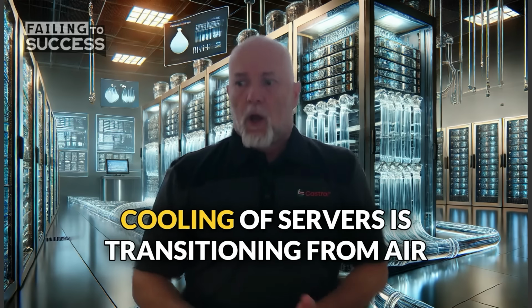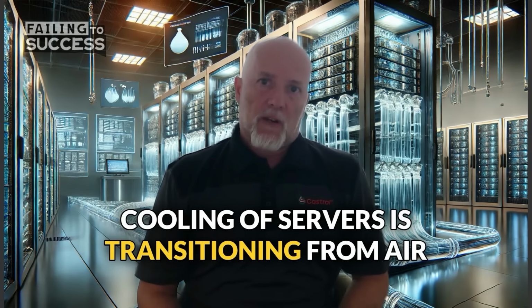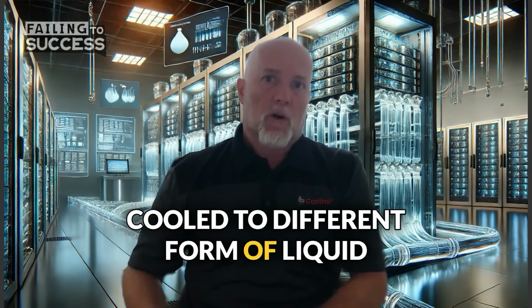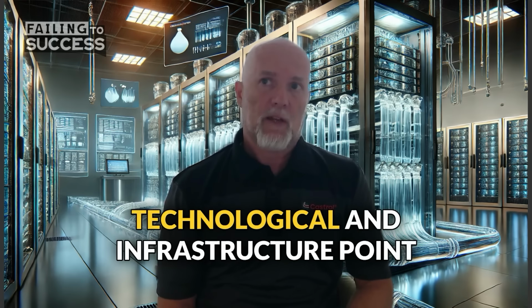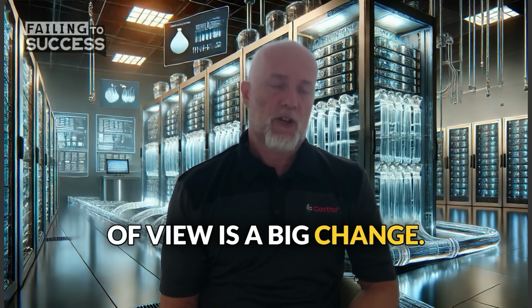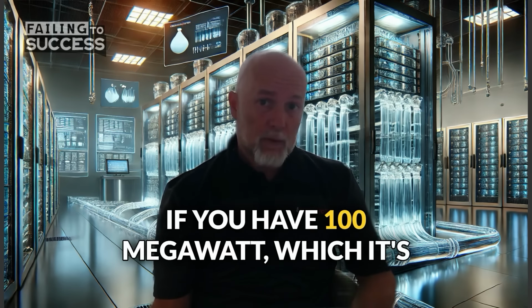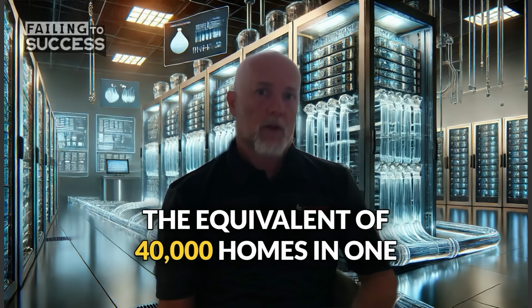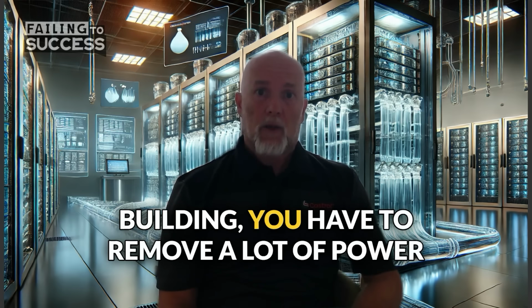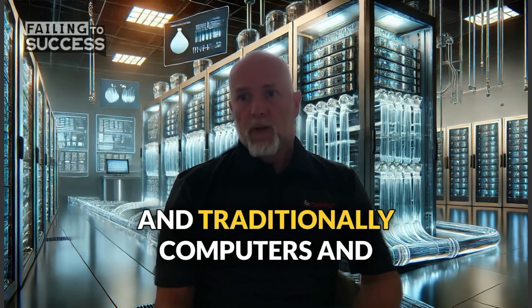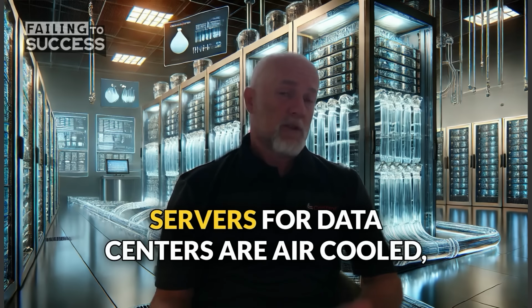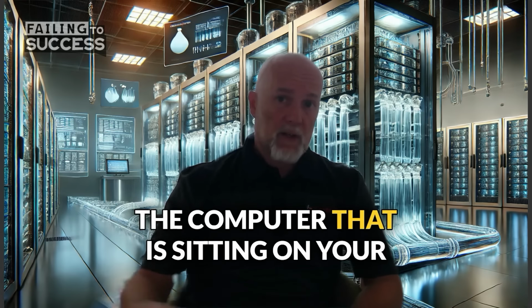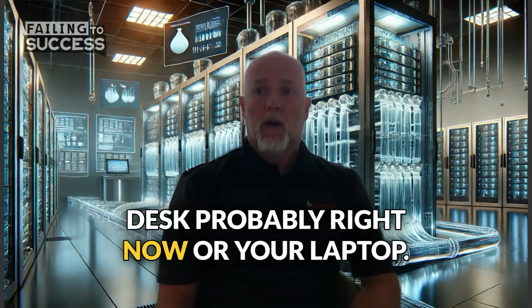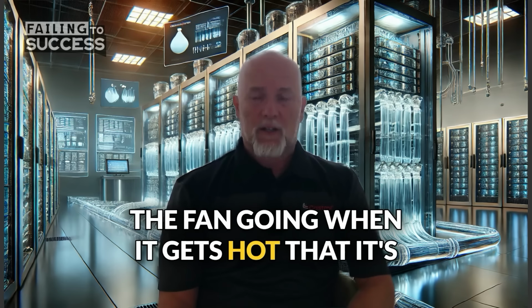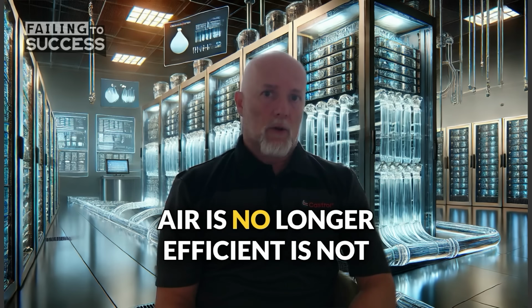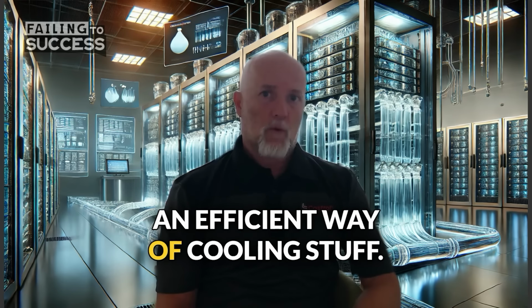The cooling of servers is transitioning from air-cooled to different forms of liquid cooling. It's a big transition—from a technological and infrastructure point of view, it's a big change. If you have 100 megawatts, which is the equivalent of 40,000 homes in one building, you have to remove a lot of power. Traditionally, computers and servers for data centers are air-cooled. The computer on your desk, or your laptop, the fan going when it gets hot, that's cooling the processor. Air is no longer an efficient way of cooling stuff.